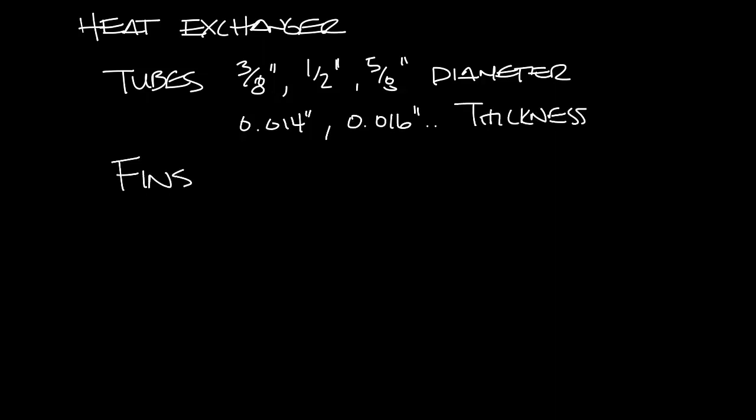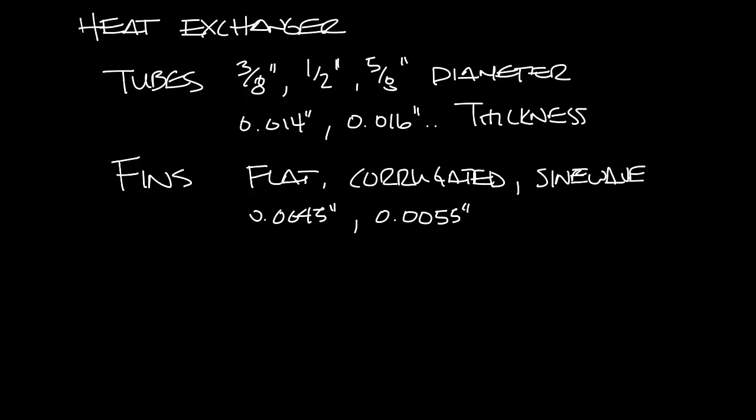The fins can be different styles. They can be flat, corrugated, a sine wave and some other shapes, and they can have different thicknesses as well, so they could be 0.0045 inches, 0.0055 inches and so on. And then you can also have different number of fins per inch, so you could have like 10 or 12 fins per inch.